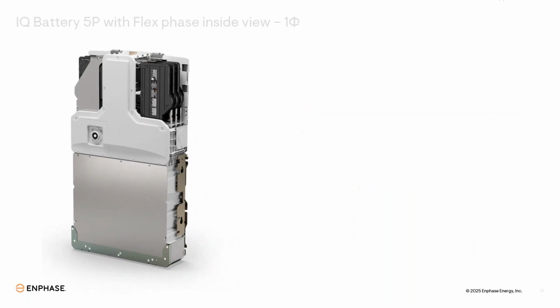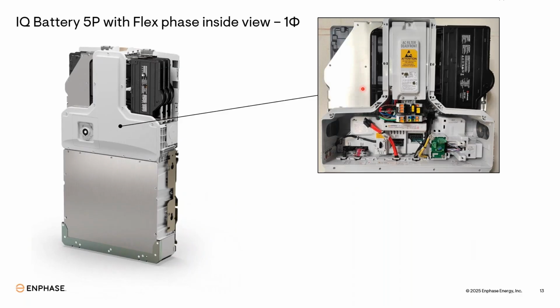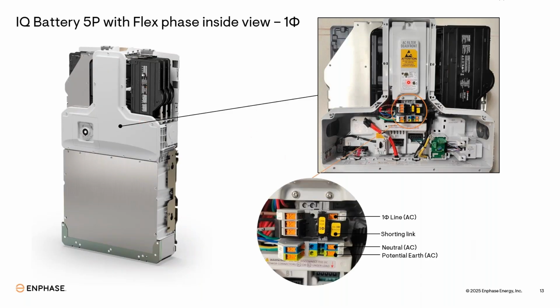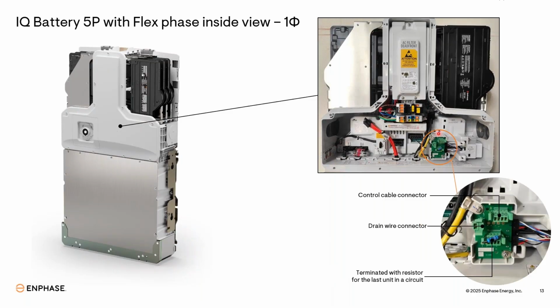And if you are going to have flex phase batteries, they look similar, but the inside wiring is a little bit different. So this is the internal wiring. Once you remove your wiring cover and take a closer look, there is a link there. If you are using only a single phase, then this link will be there. You do not need to remove this link. Connect your phase wire here, neutral wire here, earthing wire here. Your single phase connections are done. For the communication cable, you have a communication card here. You need to connect your card here. This is your control wire connectors. This is your terminator resistance, and this is your drain connector.